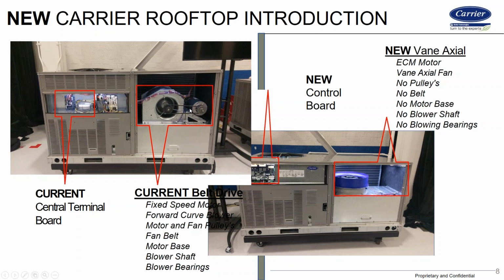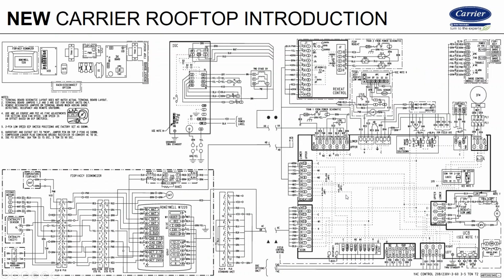So the previous unit, the belt drive unit, we had the main limit for airflow mounted right here. So it's right here on the blower deck. The new unit, the new Vane-Axial units have two limit switches in them. One's mounted on the side of the housing right here, which is a manual reset and trips at 160 degrees Fahrenheit. The other one is mounted either here, but most of the time it's mounted right down here on the side panel door. Okay, so we have two limits connected to it. Currently, the way they're set up, like in this picture, they're separate circuits. They're not wired in series. And that's where we're going to make the change. Currently, this particular limit, the manual reset limit, in the next slide, I should have a diagram here. That limit switch, and Ryan, can you guys see this okay?